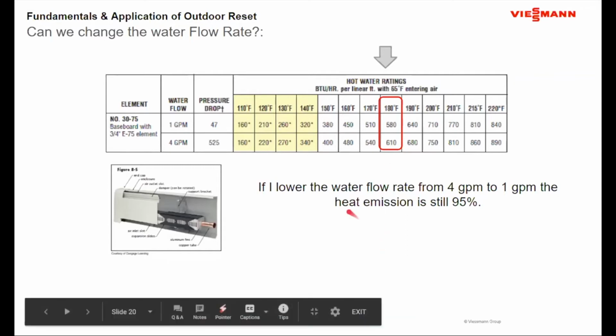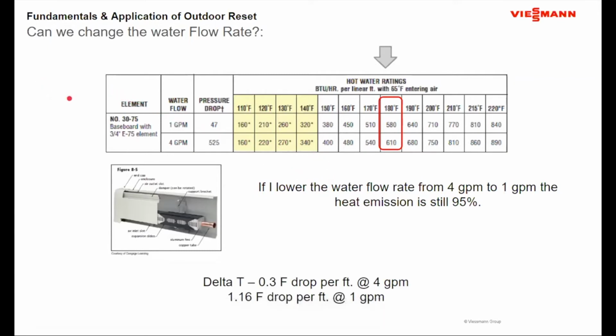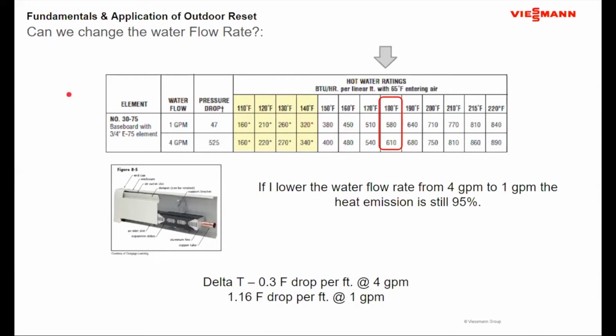The other thing to consider, especially with baseboard, is that as the water goes through the baseboard, the temperature drops each foot as the heat is being emitted. So at 4 gallons per minute, at this BTU output, I'm seeing a drop of about 0.3 degrees per foot. If I slow it down to 1 GPM to get 580 BTUs per linear foot, the drop increases from 0.3 degrees Fahrenheit per foot to 1.16 degrees Fahrenheit per foot.